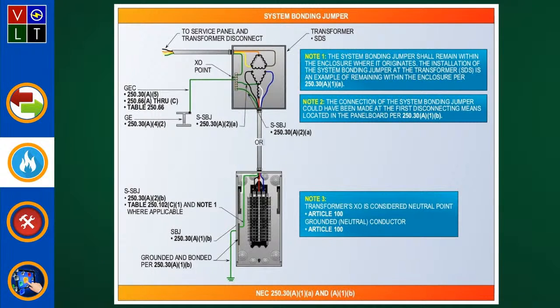Now, if I'm looking at that illustration as an example, where that system bonding jumper is installed at the source. Okay, so the source is going to be where the transformer is, right? Right. Then they're going to tell you the system bonding jumper that we size there shall connect the grounded neutral conductor to the supply side bonding jumper and all the normally non-current carrying parts of what? The metal enclosure. So it's all done there. Now, where the system bonding jumper, where I'm going down to the panel board, is installed at the first disconnecting means, then they tell you that the system bonding jumper at that point shall connect the grounded neutral conductor to the supply side bonding jumper, the disconnecting means enclosure, and also the equipment grounding conductors. But there's one thing you've got to be careful of here.